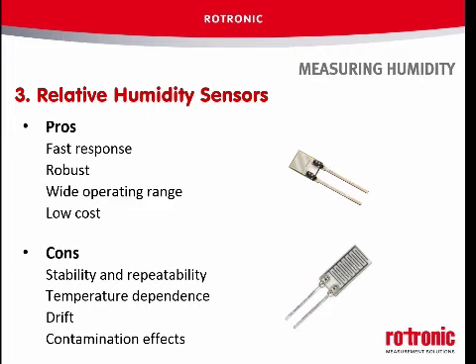So people have developed these polymers. They find that they seem to respond fairly linearly to this measure of humidity. They don't normally respond to absolute humidity, so things like mixing ratio, they're not linear to those. They do actually respond to relative humidity, and they are then factory adjusted in some way to give accurate RH measurements. And this is an example of a typical sensor.